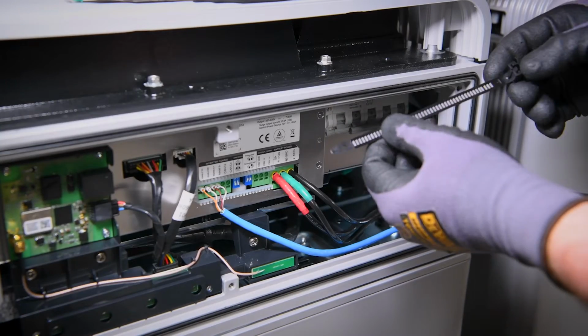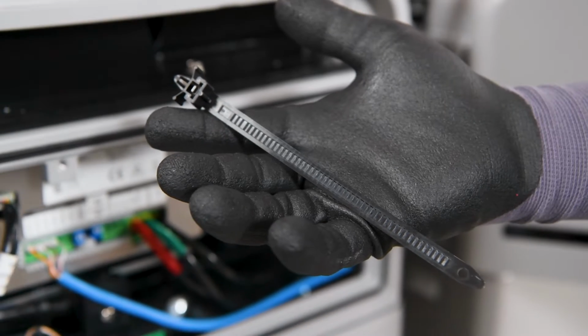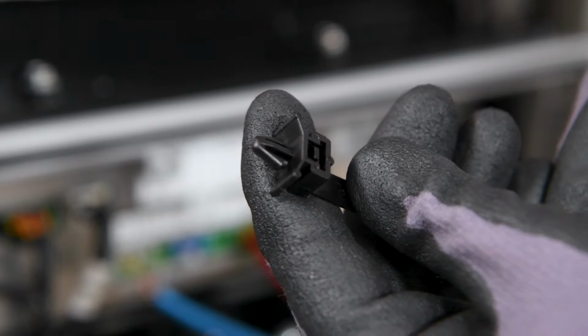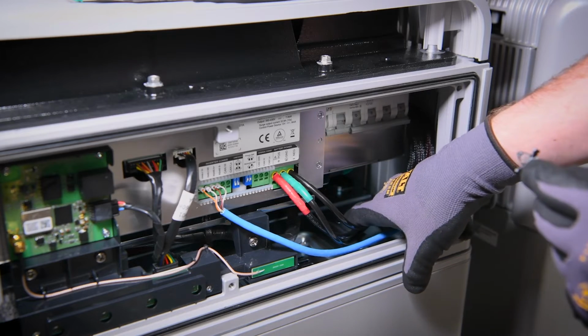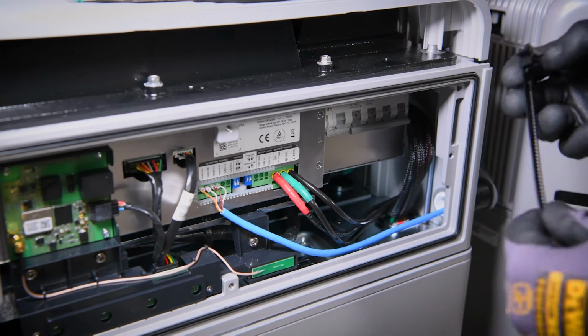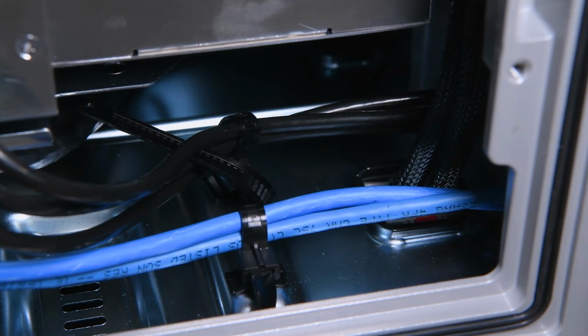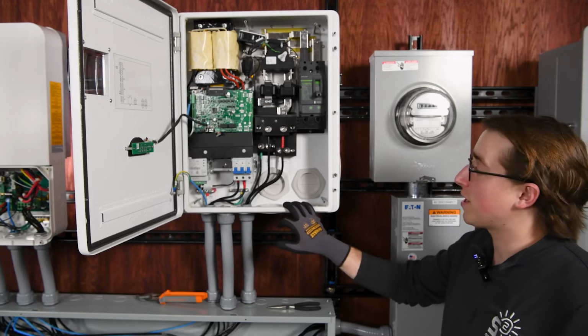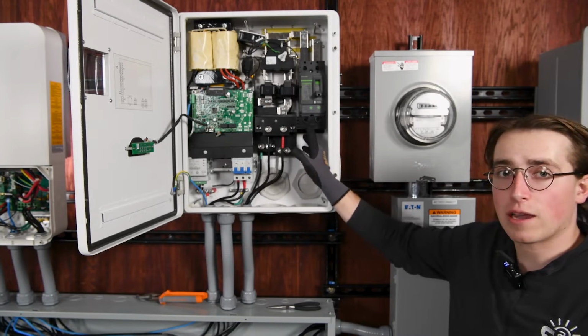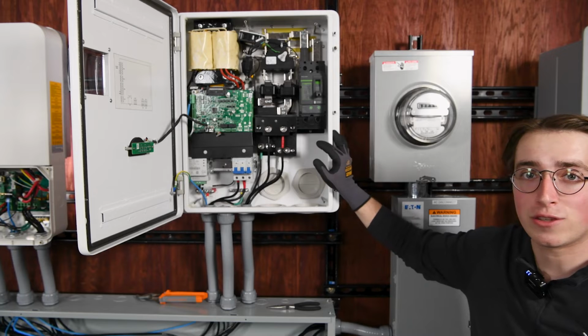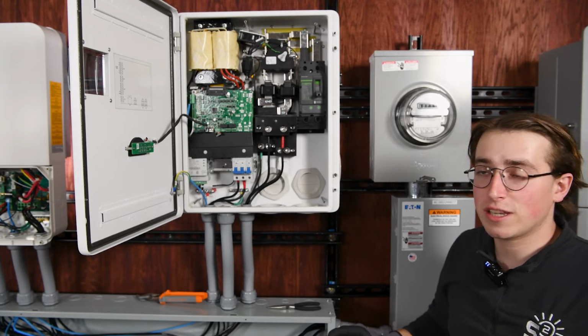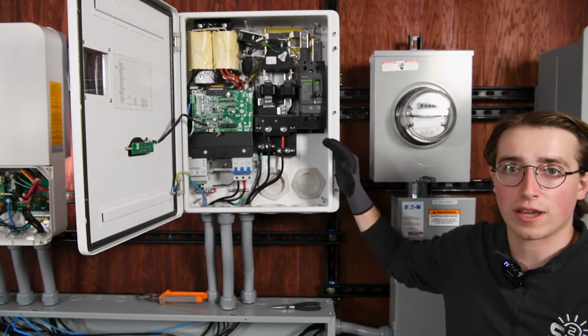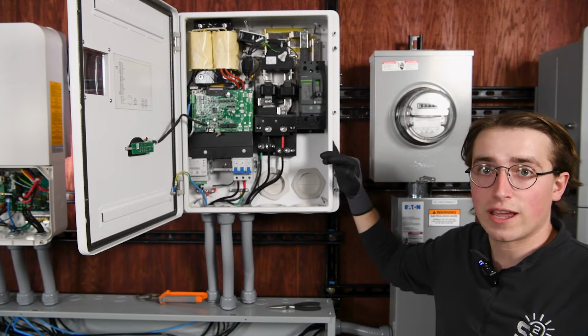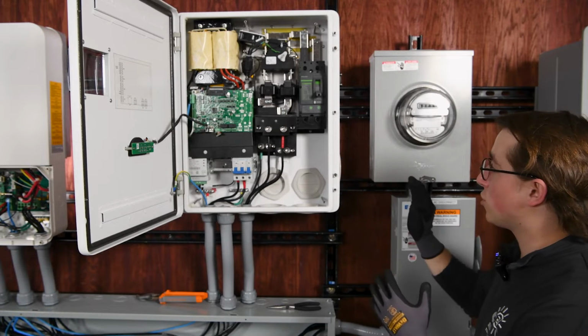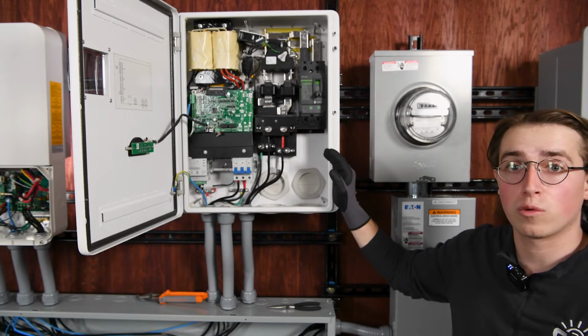With the LG packaging, we also get these neat little zip ties that have this point on the tip here. This point will actually clip to the base plate inside the battery. This is a great option for keeping your hot conductors, or your positive and negative conductors, separate from your communication cable. One of the final steps in commissioning and installing the SYN is going to be connecting our grid conductors. The SYN is rated for service entrance capabilities, which means that you can connect your meter directly to the SYN, but you'll always need to contact your local AHJ, or authority having jurisdiction, to ensure that this setup is proper for their rules and regulations.